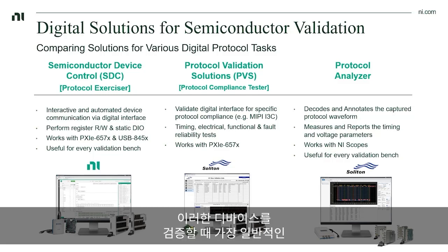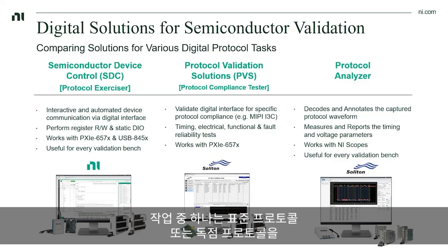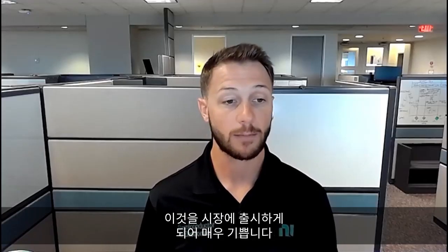One of the most common tasks that you have to do when validating these devices is to communicate to the part using a standard protocol or a proprietary protocol, and then being able to do some register read writes or static DIO operations for controlling load board or eval board elements like relays. And so we were really excited to bring that to market.